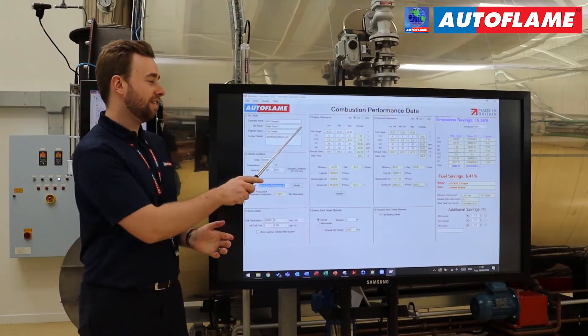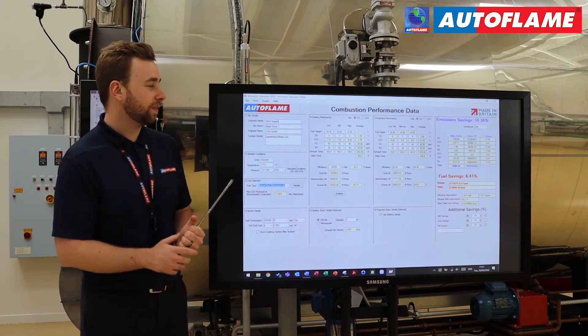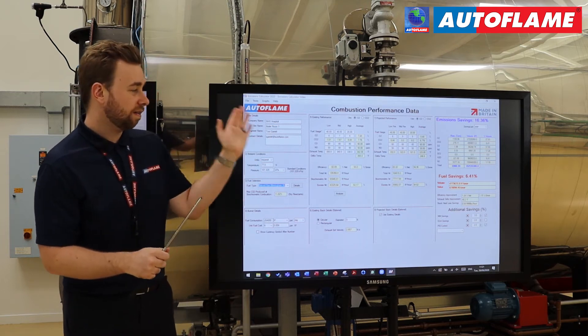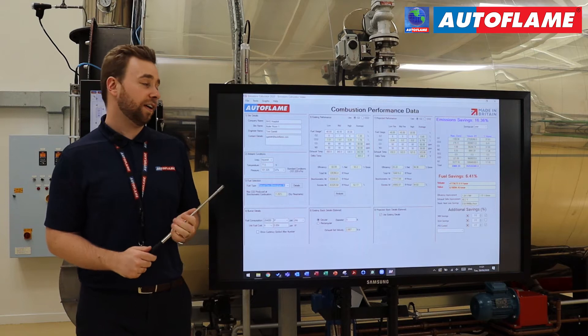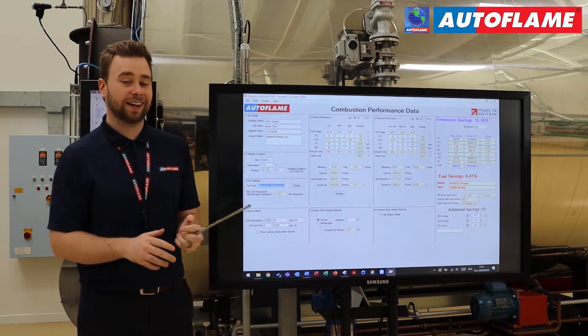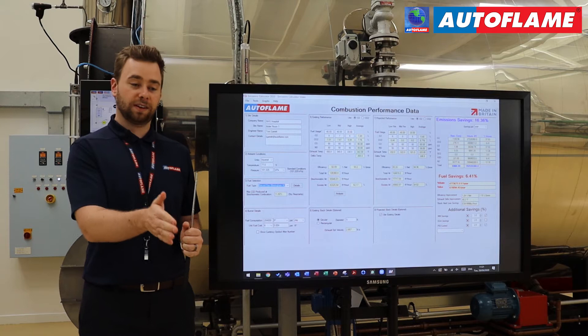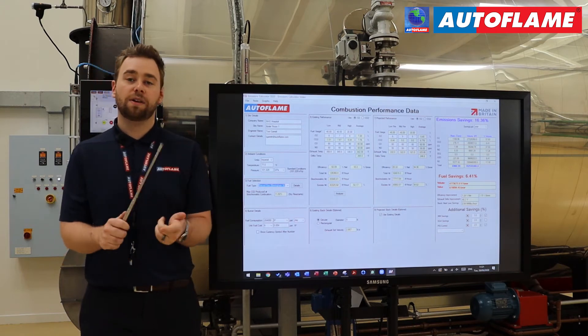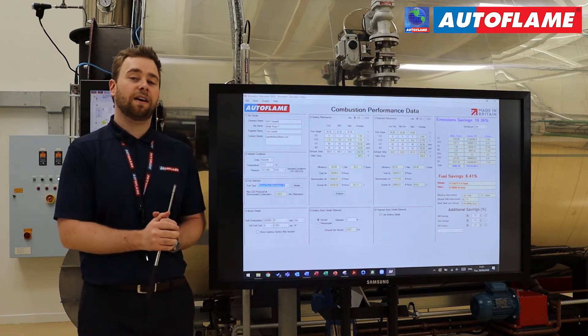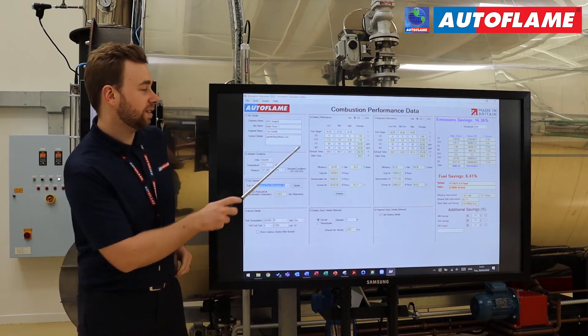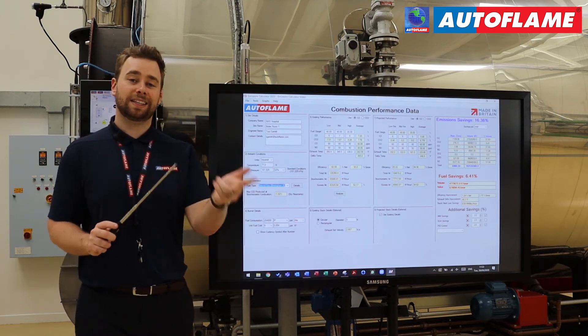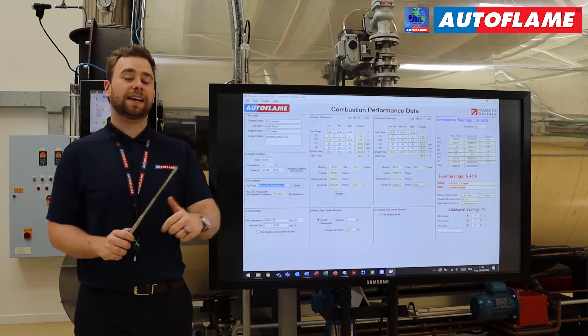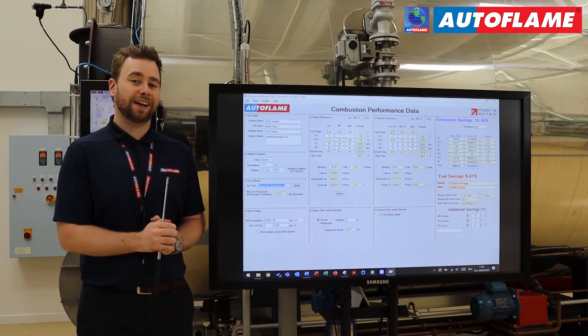Thanks for the information, Dek. Now let's input it into our emissions calculator. We have low fire, mid fire, and high fire boxes to fill in. We need to tell the calculator how often the burner sits at low fire, mid, and high — so I've input 40% at low, 40% at mid, and 20% at high fire. I'm going to input the O2 readings as 8%, 7%, and 6% between low and high fire. The CO and NO are constant at 80 ppm and 50 ppm respectively.